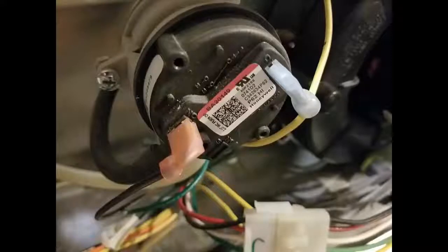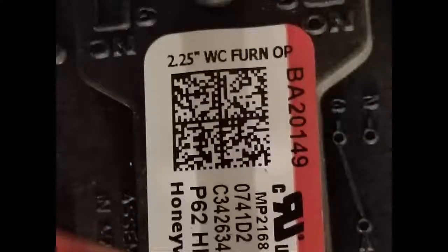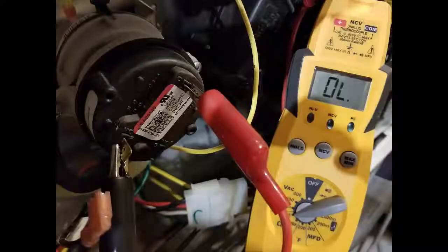The pressure switch is a safety device that is basically just a glorified light switch, which is always in the open position, or what we call normally open. When it senses the correct pressure created by the inducer motor, either a positive pressure or a negative pressure depending on the unit, it closes, telling the circuit board that the system is okay to proceed to the next sequence of operation. This particular pressure switch needs to see a minimum of 2.25 inches of water column of pressure before it will close. Pressure switches are relatively easy to troubleshoot. All you have to do is remove the low voltage wires leading to the switch, make certain that the power is off before you're doing this, and then connect the leads of an ohm meter to the terminals on the switch.